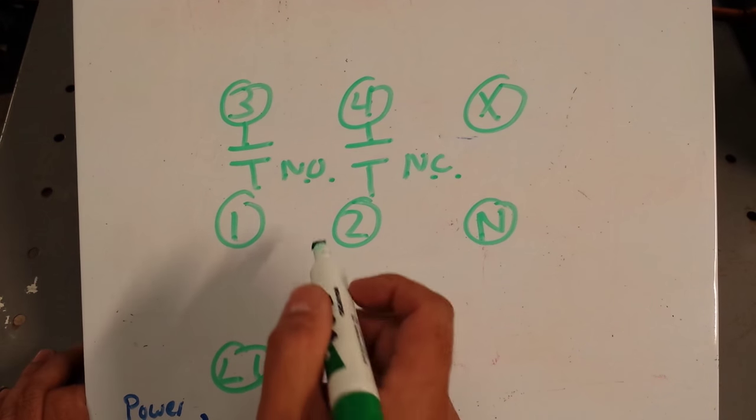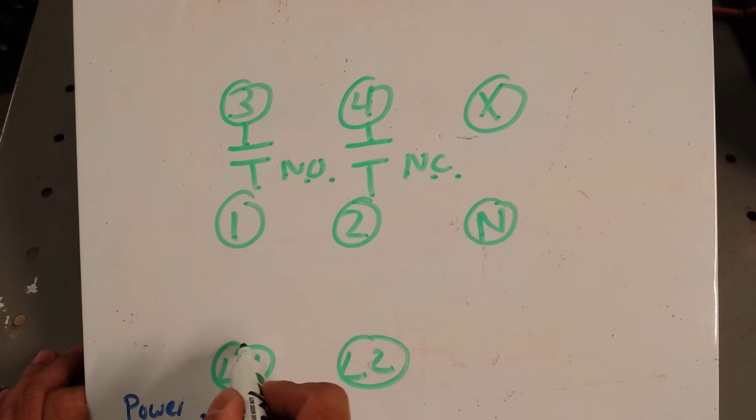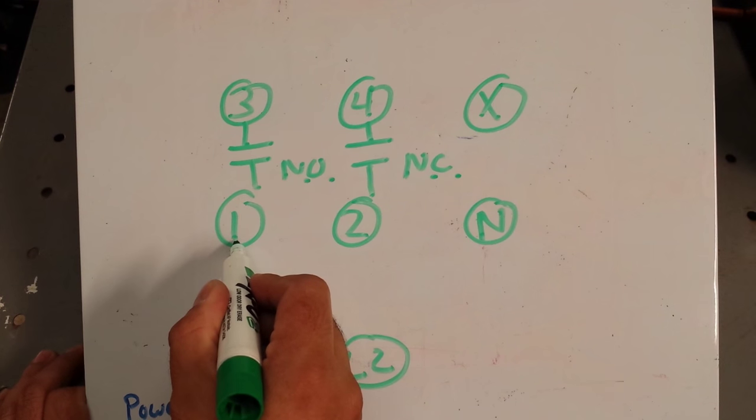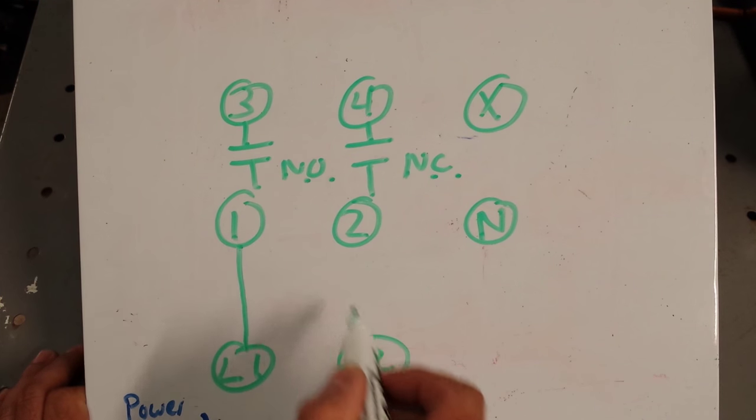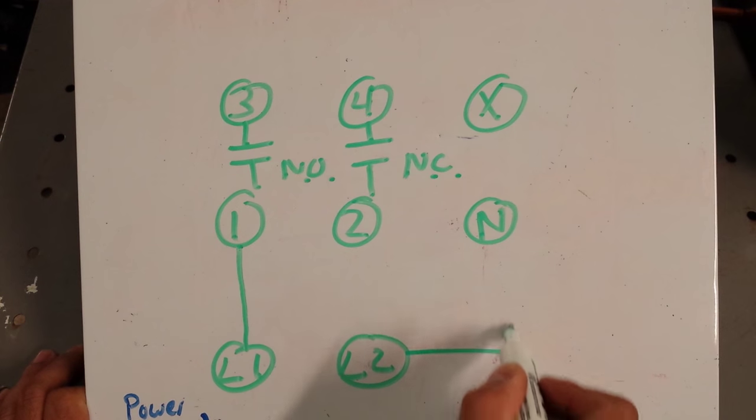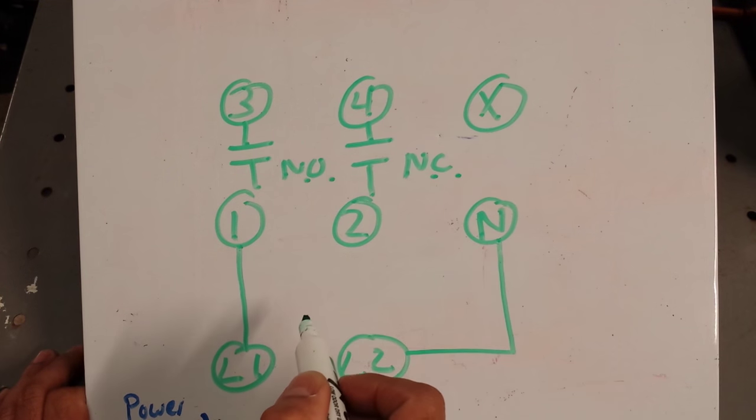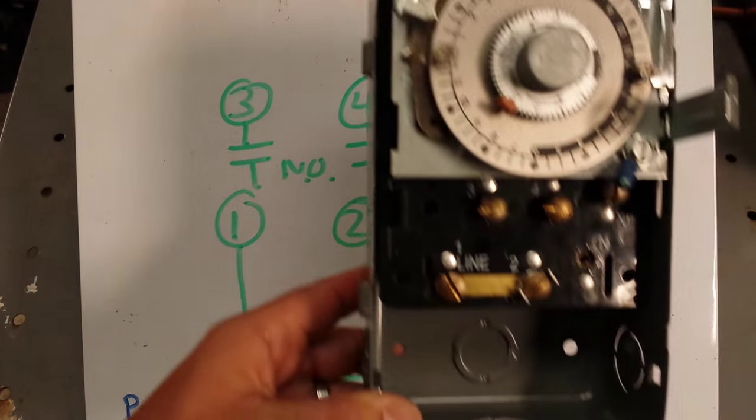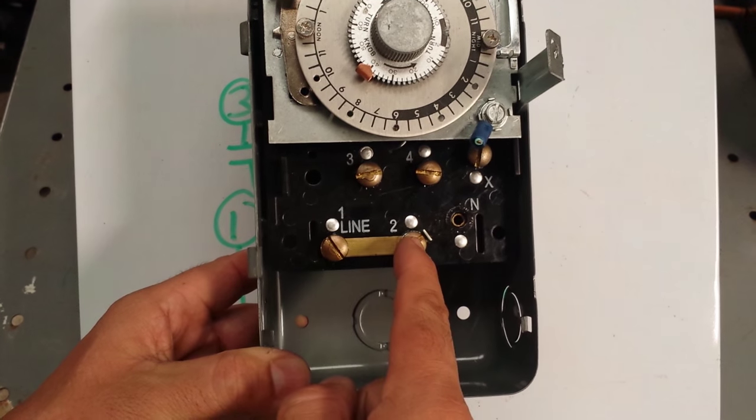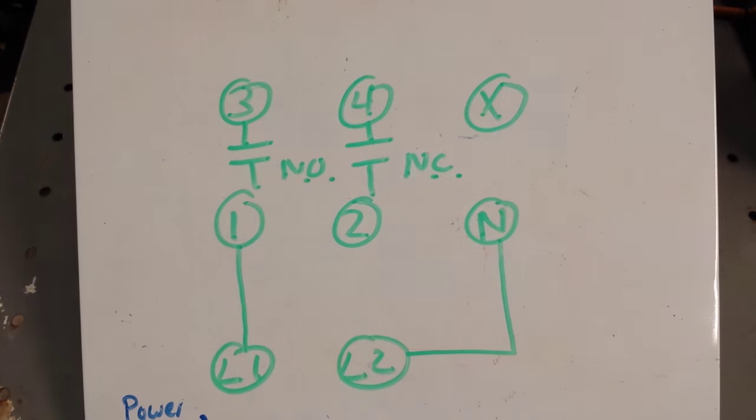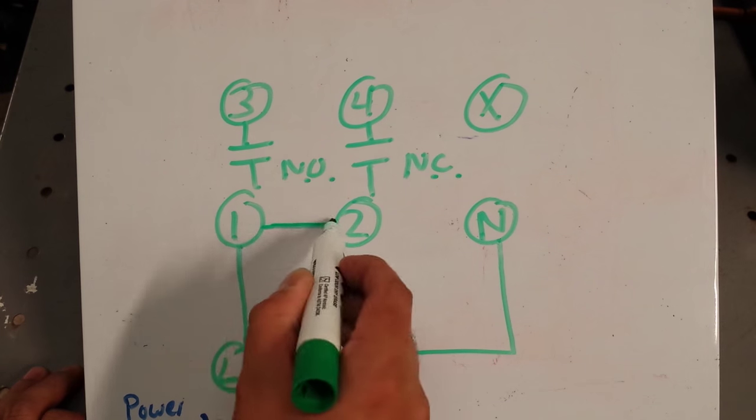So if you remember correctly, we had L1 feeding our terminal 1 to our time clock. And then L2 feeding power to terminal N. You'll also remember, and I'll show that clock again, there's a jumper between 1 and 2 here. So L1 feeds 1, and then there's a jumper between there. So L1 actually feeds terminals 1 and 2.